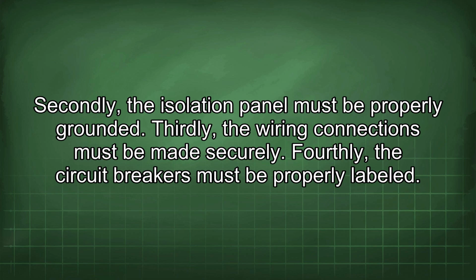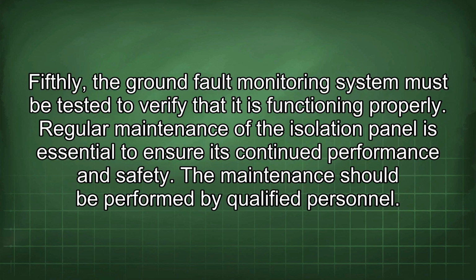Fourthly, the circuit breakers must be properly labeled. Fifthly, the ground fault monitoring system must be tested to verify that it is functioning properly. Regular maintenance of the isolation panel is essential to ensure its continued performance and safety. The maintenance should be performed by qualified personnel.